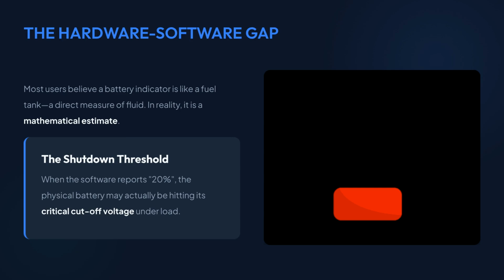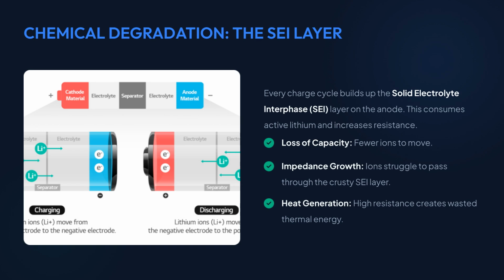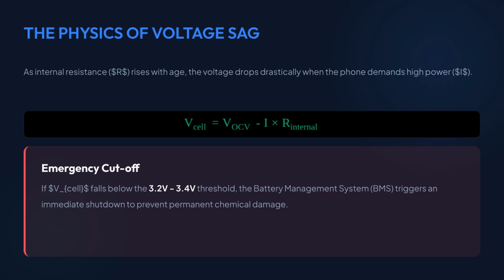This is the hardware-software gap. Chemical degradation, specifically the buildup of the solid electrolyte interphase layer, consumes active lithium, increases resistance, and leads to heat generation. The physics of voltage sag means that as internal resistance rises, the voltage drops drastically under high power demand. The battery management system triggers an immediate emergency cutoff if the voltage falls too low to prevent damage.